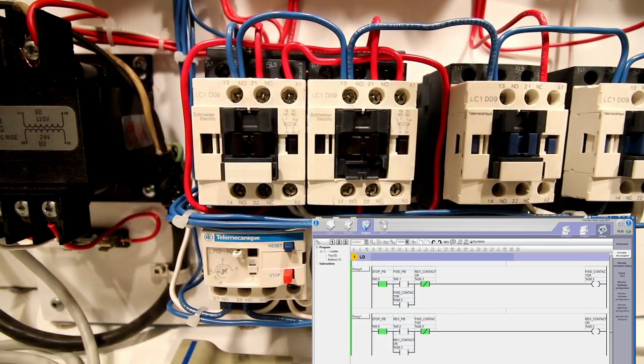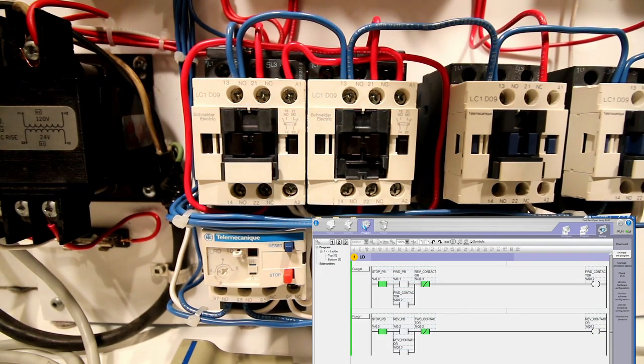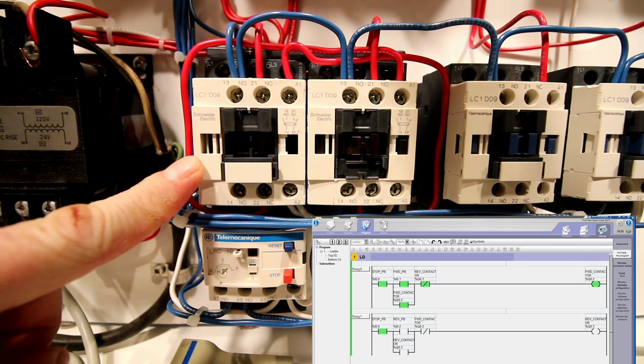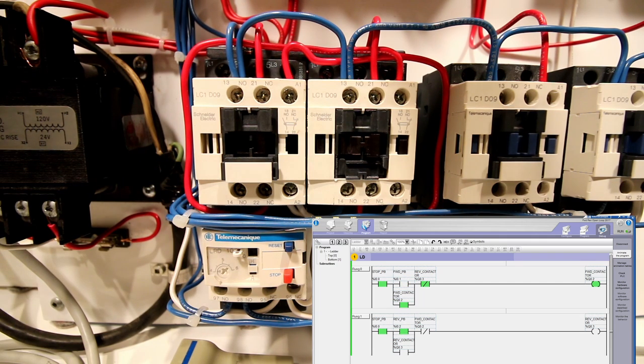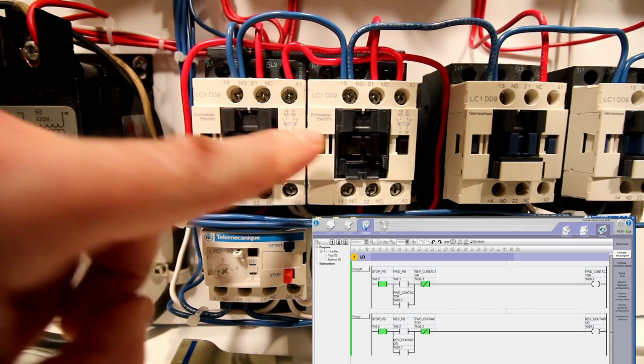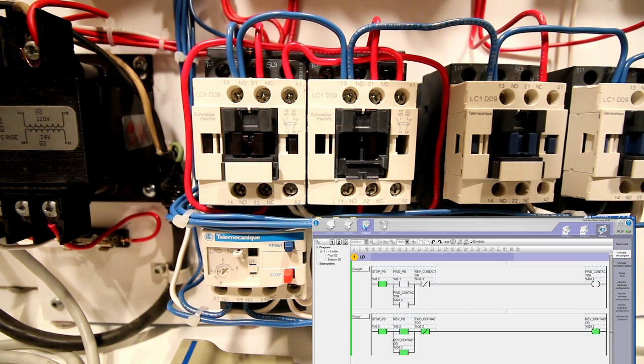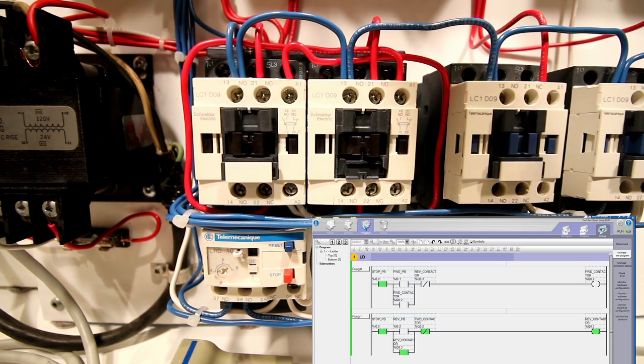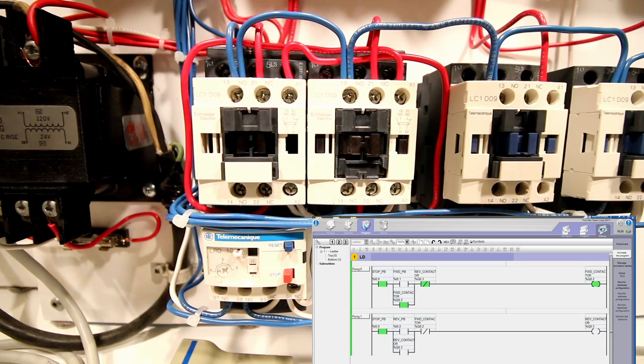Let's hit the forward contactor and watch the first contactor pull on. Trying to hit reverse while forward is energized — nothing happens. Hit stop, that contactor pulls back out, hit reverse and that contactor turns on. I can hit forward and nothing happens. So I'm in the forward direction, and now I'm going to trip the overload.